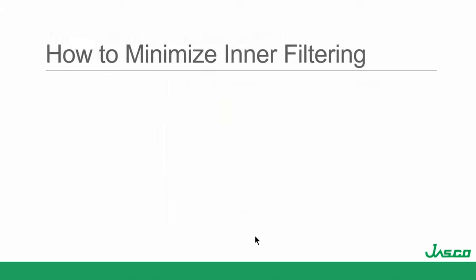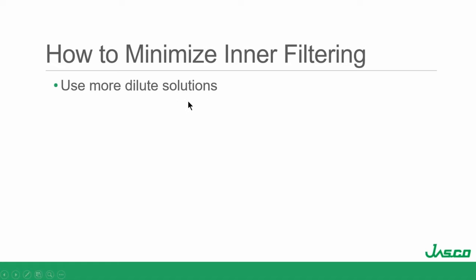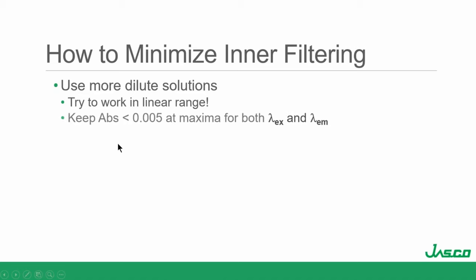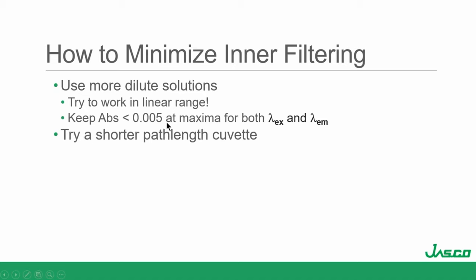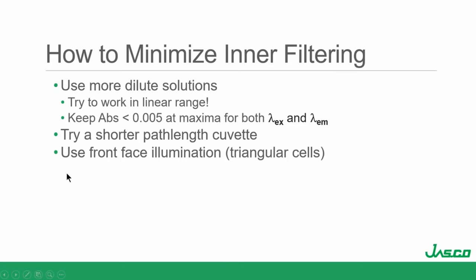How do we minimize inner filtering effects? Of course, use more dilute solutions if we can — take advantage of the sensitivity of fluorescence and be aware that you're working in the linear range. Textbook recommendations: keep absorbance at 0.005 at the maxima for both lambda excitation and lambda emission. If you can't control concentration, consider a shorter path-length cuvette on the excitation and/or emission direction. Front-face illumination and triangular cells can also be used.